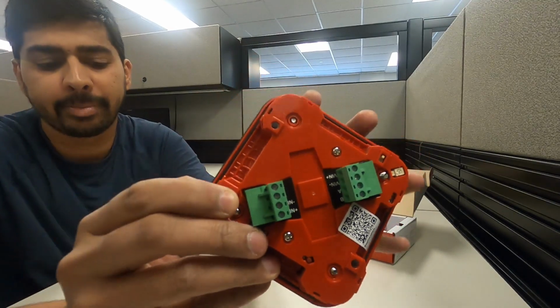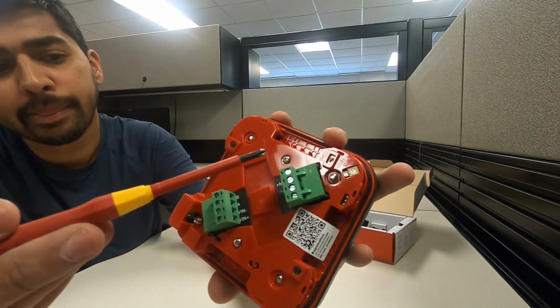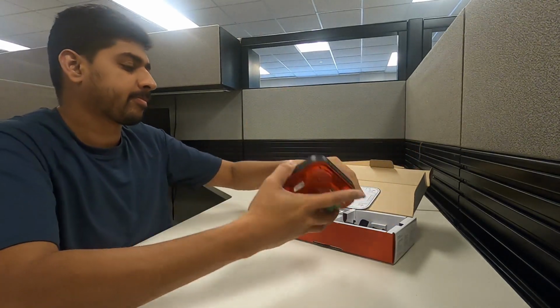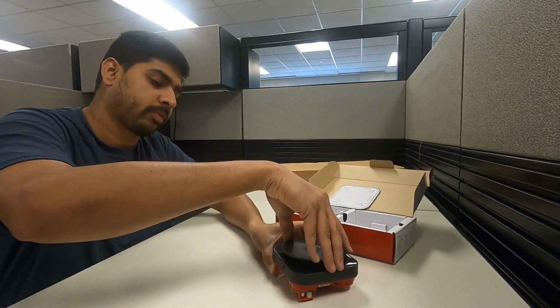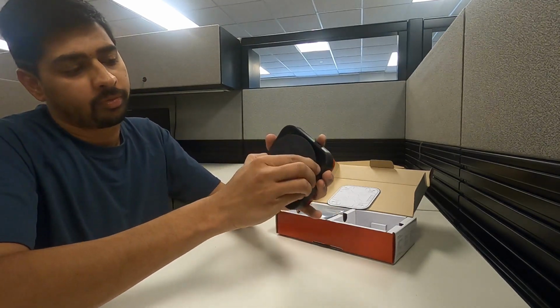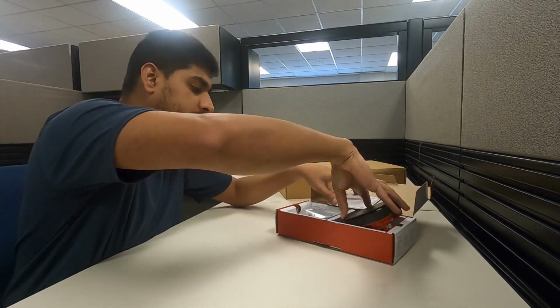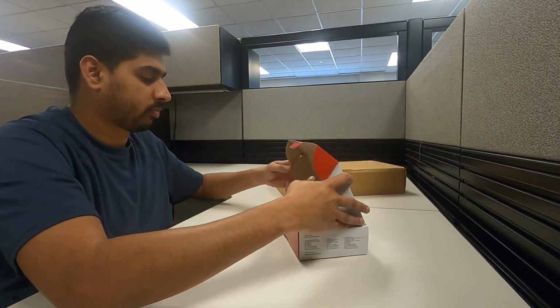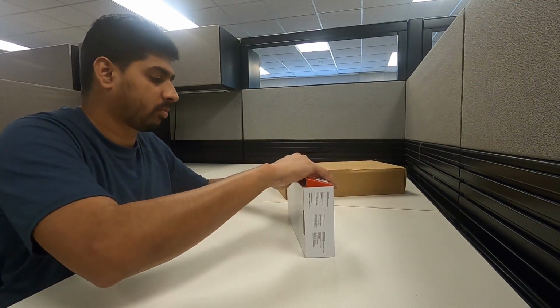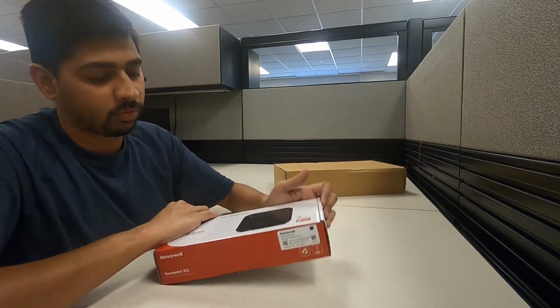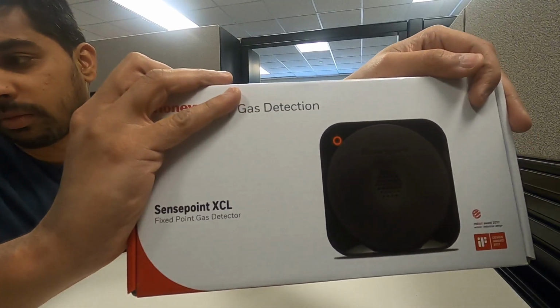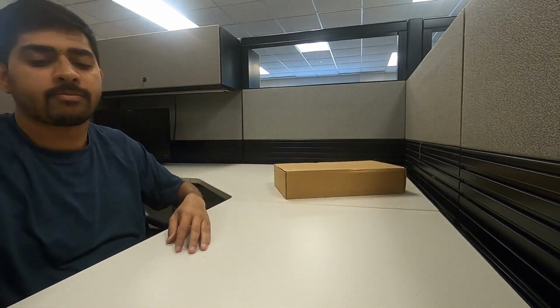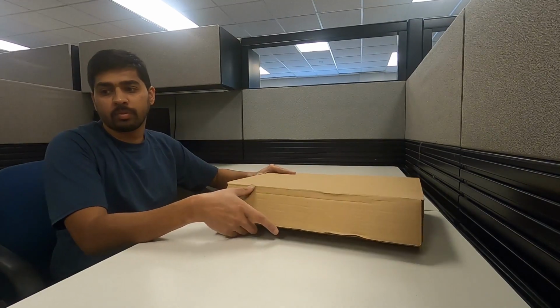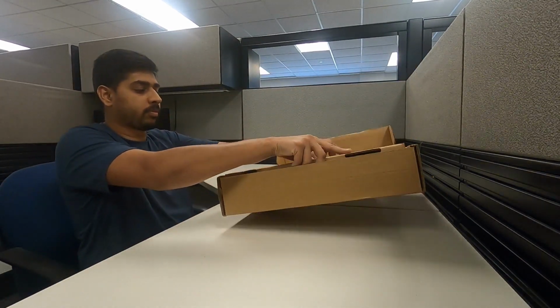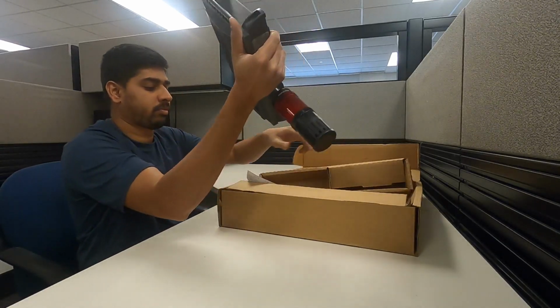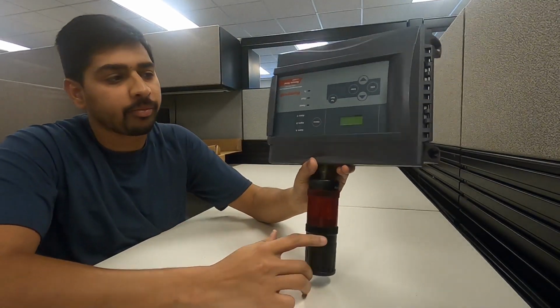The sensors will be placed to cover a certain radius of the garage space throughout the garage. These sensors will communicate over a daisy chain with BACnet or Modbus coming back to your controller to communicate the signals, or it can be a current signal coming back from individual sensors, or all of these can communicate over a Wi-Fi mesh network and then communicate back to your controller where you record all the data. Depending on how your job site is, if you can pull more and more wires, you'll take the current signals, but your labor charge of pulling wires may be higher than the actual sensors and the job itself. And you might have to go to a daisy chain with all of these communicating over a single loop of BACnet or Modbus.